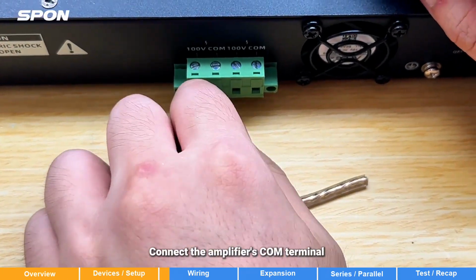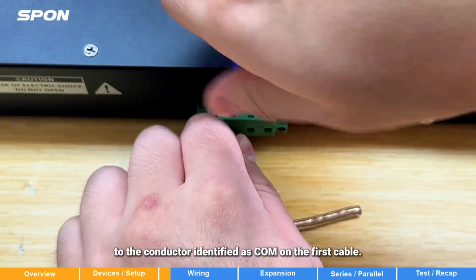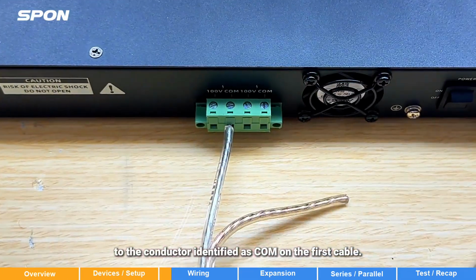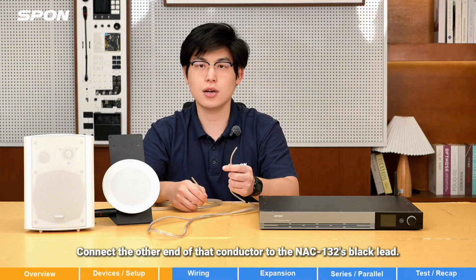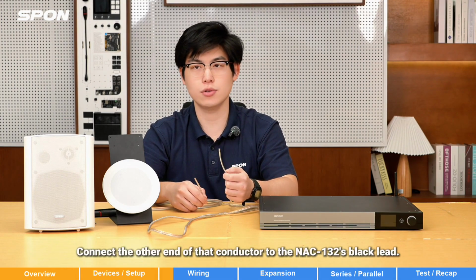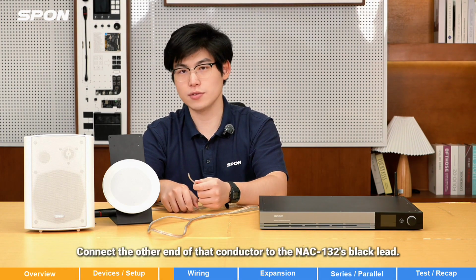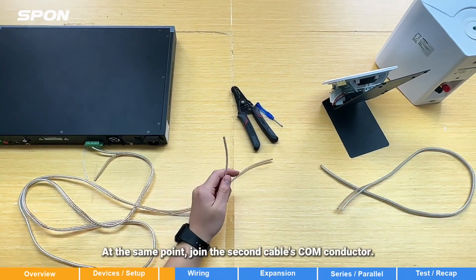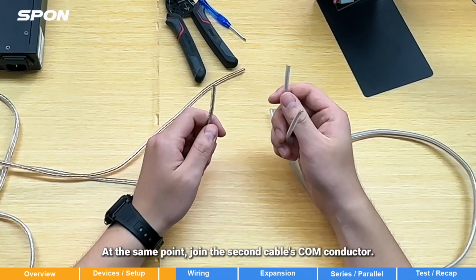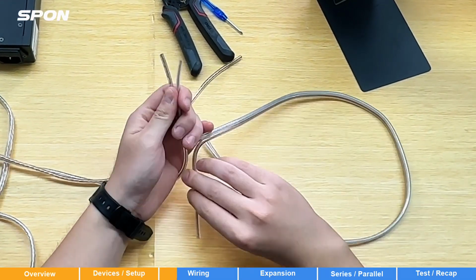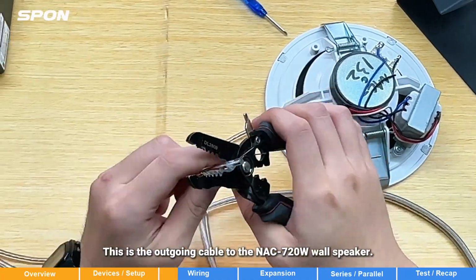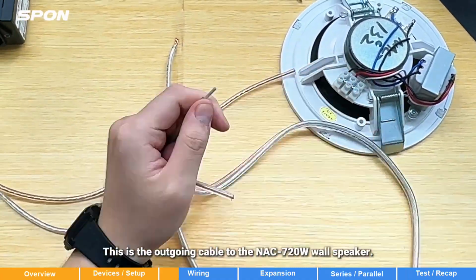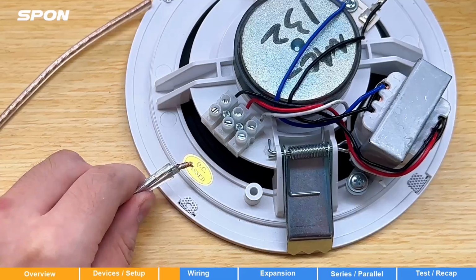Connect the amplifier COM terminal to the conductor identified as COM on the first cable. Use the other end of the same cable to connect to the NAC-132's black conductor. At the same time, combine the second cable's COM conductor, which is the outgoing cable, to the NAC-720W wall speaker.